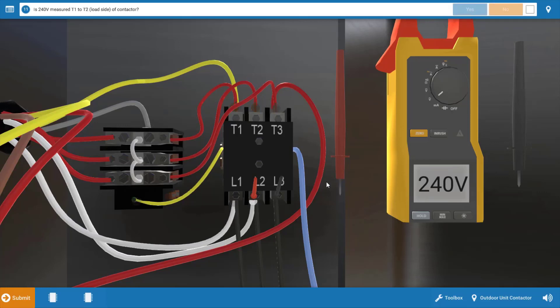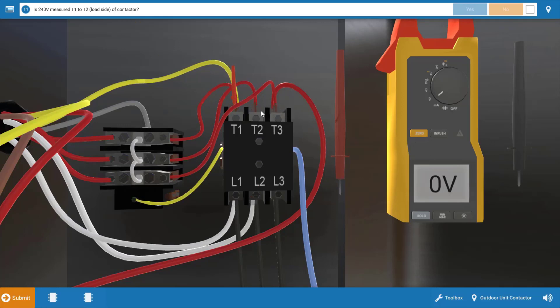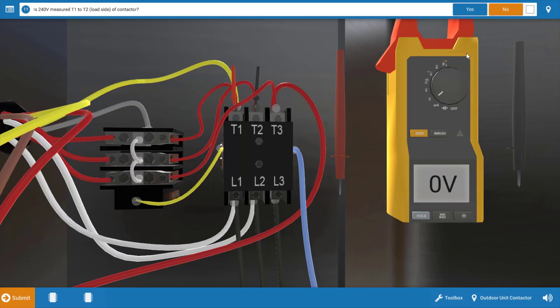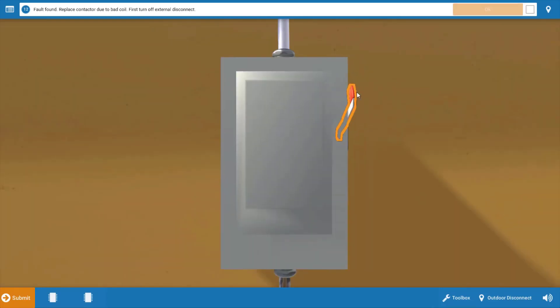So we're going to click yes on the procedure guide, and our next step is to check the load side of the contactor. So we'll begin by checking T1 and T2, which will verify if the contacts are actually closed, and we have zero volts here. So those contacts, or at least one of those contacts, are not closing. So we're going to click no on the procedure guide, and we're going to kind of determine at this point that we have power to the coil, so it should be energized, and it should have pulled those contacts in. So our contactor is going to be the fault here.